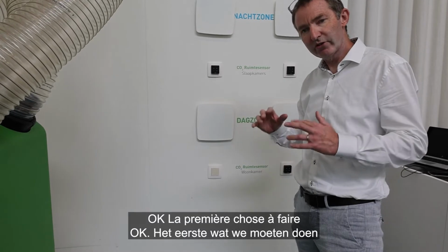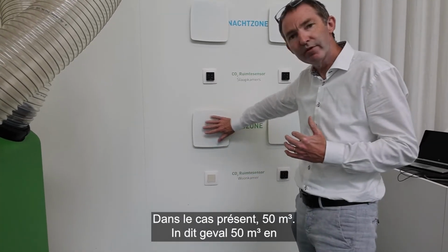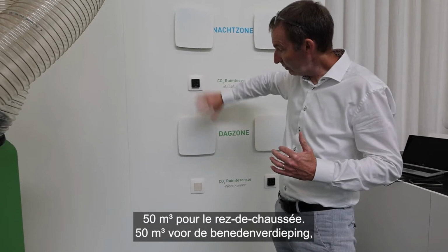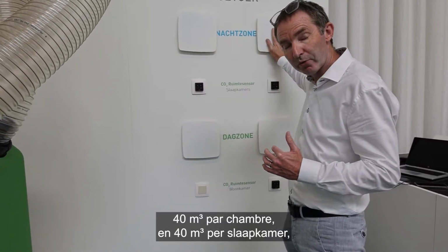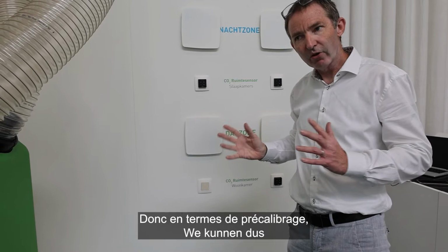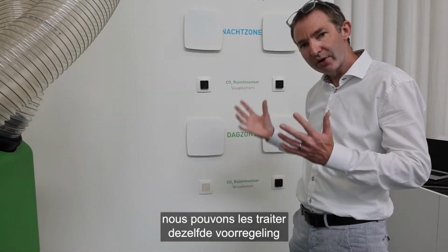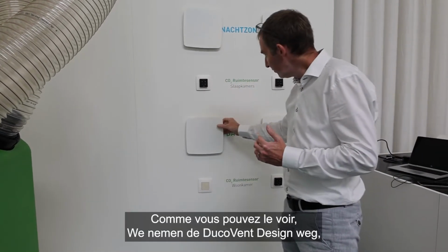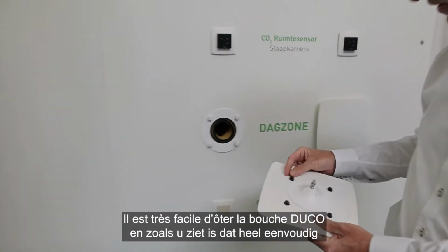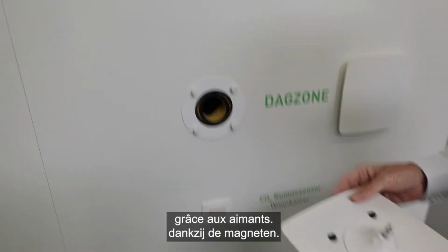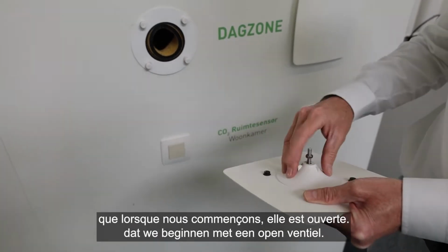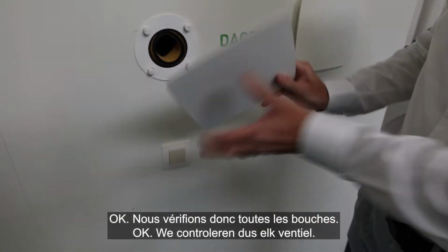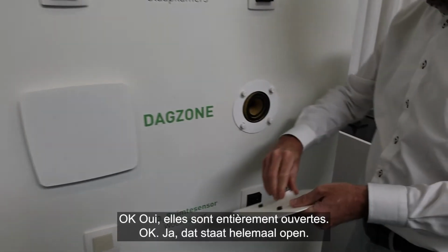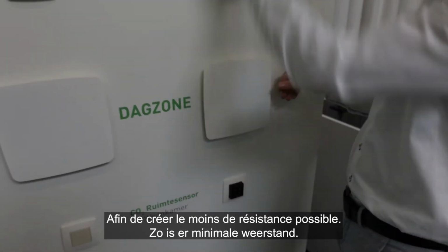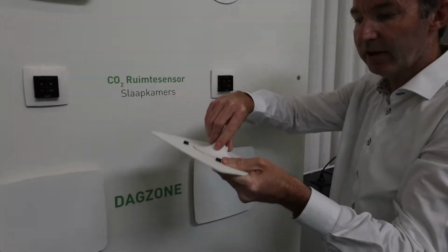The first thing to do is to actually pre-calibrate. In this particular case, 50 cubes for the downstairs, 40 cubes per bedroom. It's actually quite similar, so in terms of pre-calibration, we can treat them the same. When we take off the DucoVent design, as you can see, it's nice and easy with the magnets. We always need to make sure that when we start off, it's open. So we check every vent. Yes, it's open to the fullest, so that least resistance is created. We do that with every vent.